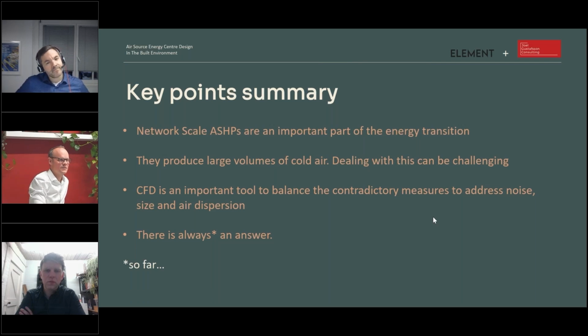I don't know of a scheme, but we had feedback from one of the larger European manufacturers that there was an installation, they did proclaim not their own, and I'm not name dropping anyone, where it failed because of air recirculation problems. And you can imagine, looking at the scale of these things, they're not cheap. The solutions in practice on the ground are probably not available as retrofits, and there are major issues that will result from that.